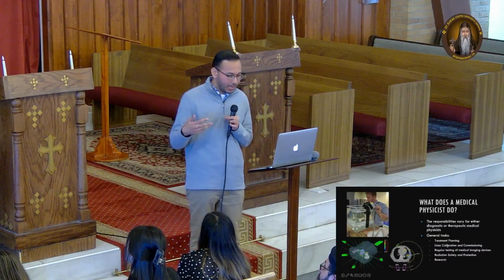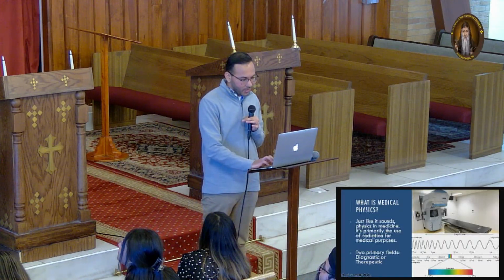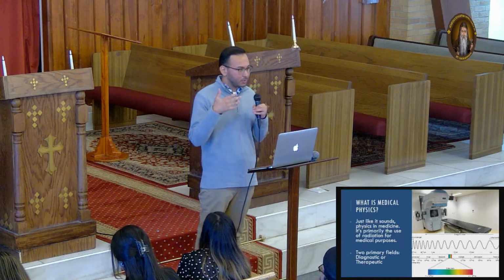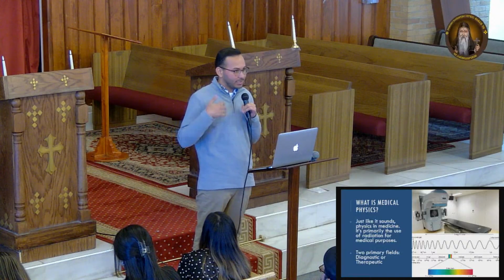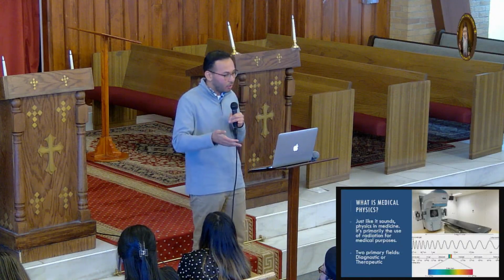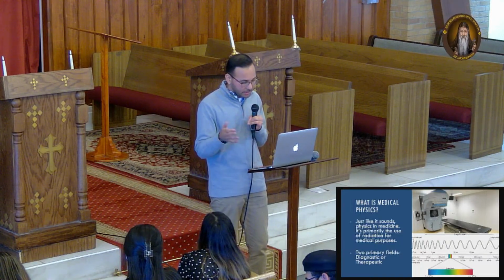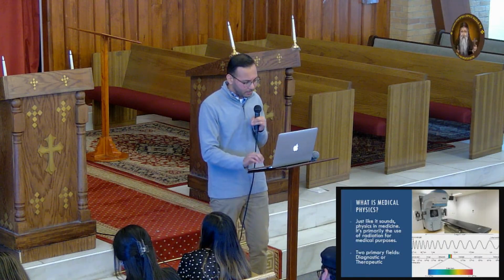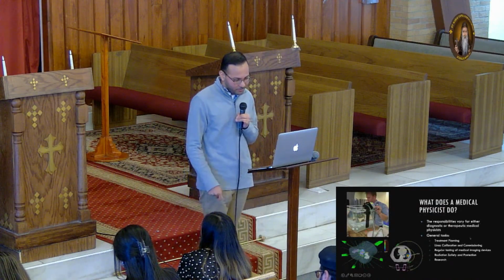Next, we'll also do LINAC calibration and commissioning. That linear accelerator, the machine that I showed you, we need to test daily, monthly, and annually to make sure it's producing the correct amount of radiation, that it's not telling us one thing and actually producing something else, which could harm the patient. We test these machines daily, monthly, and annually for all sorts of different things. I'm not going to get into it, but that's another thing that we do.